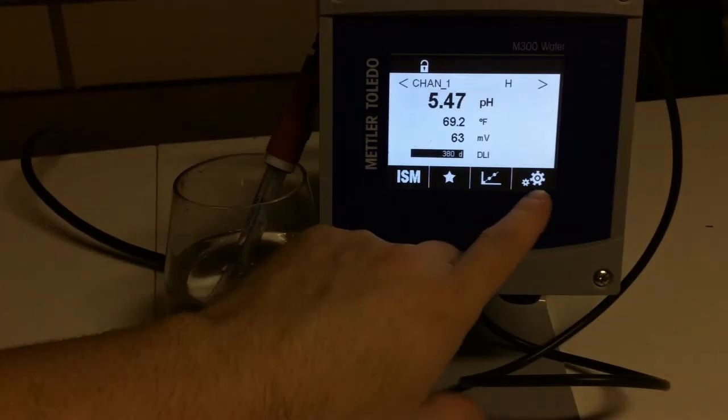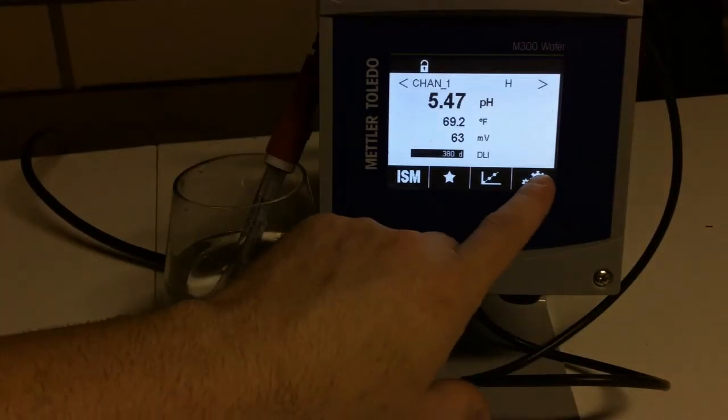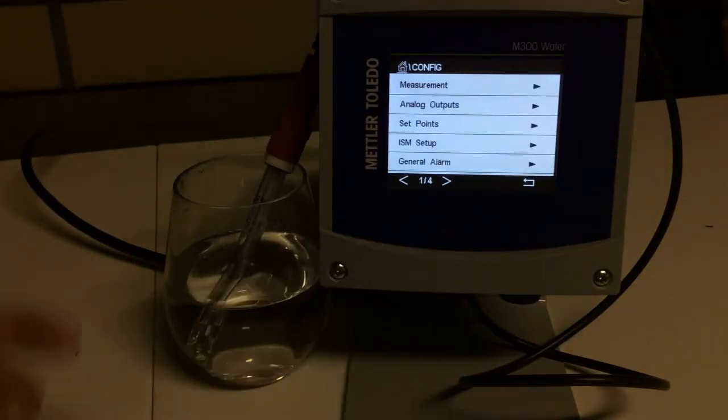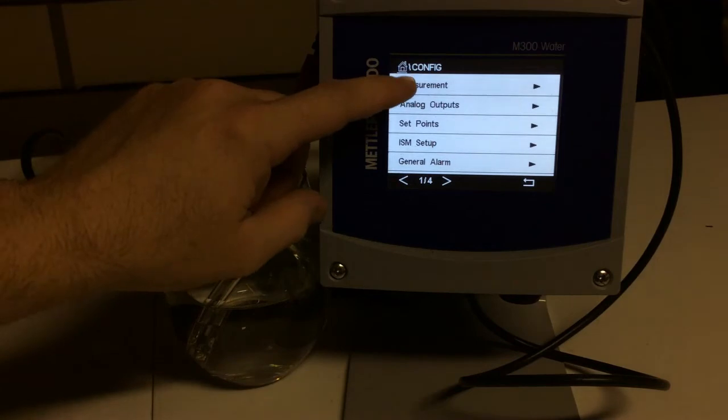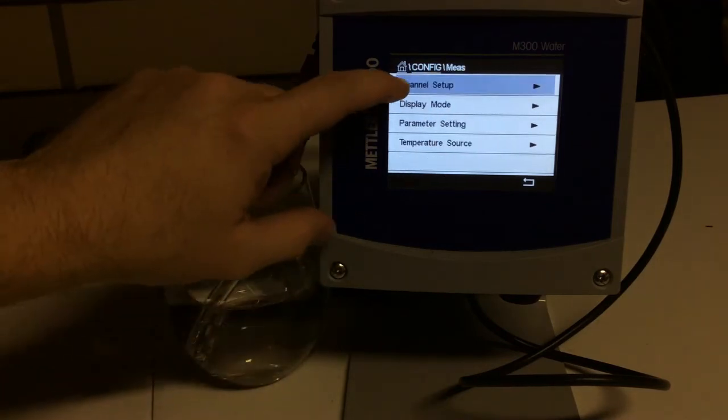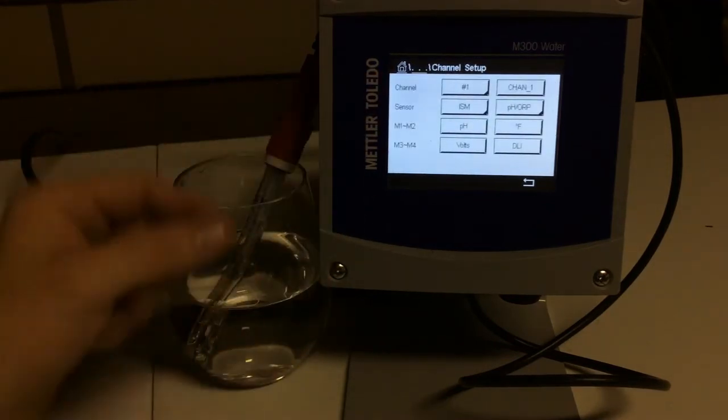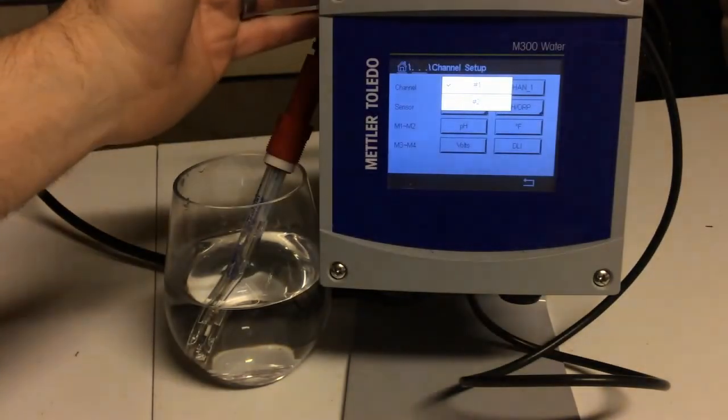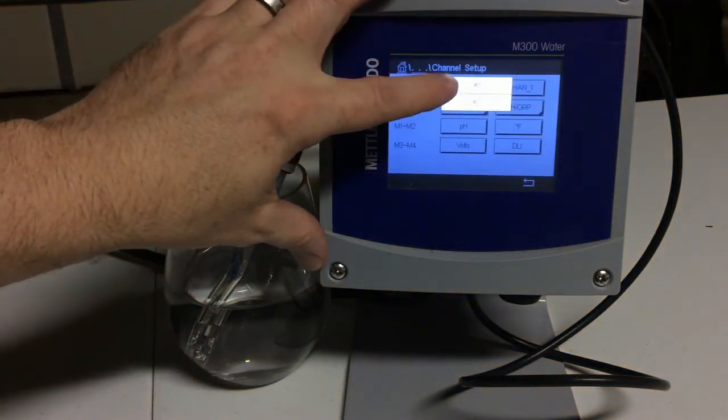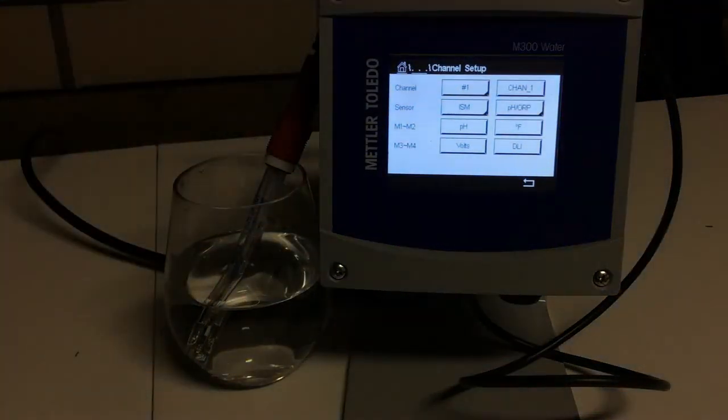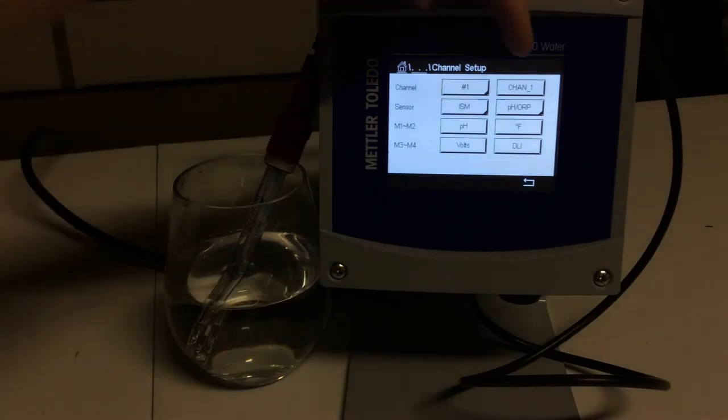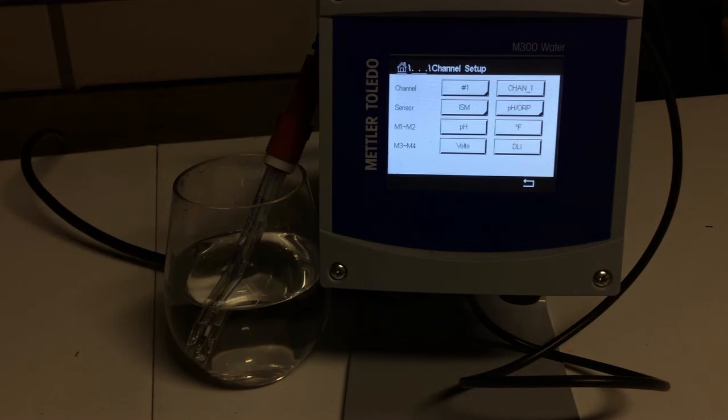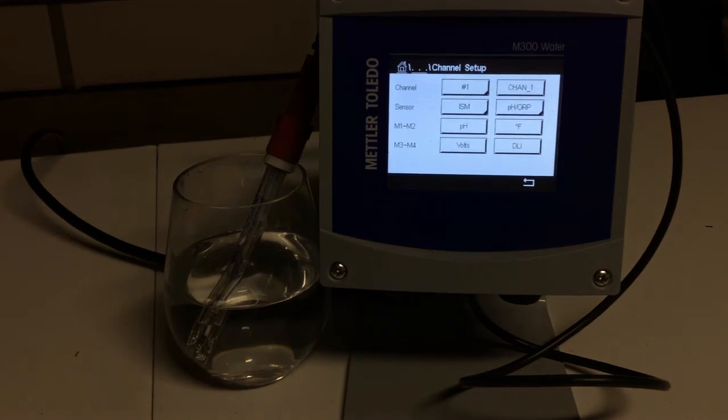Now I'm going to walk you through a few basic steps of setting up different parameters with the channel display. And it's pretty simple and easy to use via the touch screen. And so now we'll go to our final tab, which is our settings tab. If we come here, this is where we can set everything up. So if we hit measurement, we want to do channel setup. This is a two channel, so I can hit one or two, and I can see channel two if I wanted to, but we only have one setup, so channel one. With this button over here, I can name it whatever I would like. So if it's, say, plant one boiler or UAN or whatever it might be, you can name it.